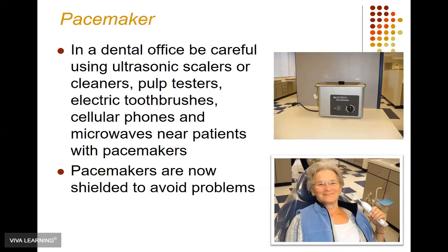Those procedures performed in the dental office that are considered safe for pacemaker and ICD patients are dental radiographs, the use of dental handpieces, composite curing lights, sonic and piezoelectric ultrasonic scalers. Dental devices in which some controversy exists as to their safety with pacemakers and ICDs are older ferromagnetic ultrasonic scalers, magnetostrictive ultrasonic scalers, TENS units or transcutaneous electrical nerve stimulators, ultrasonic cleaning baths, and electrosurgical units. Malfunction was more common in older implant models.